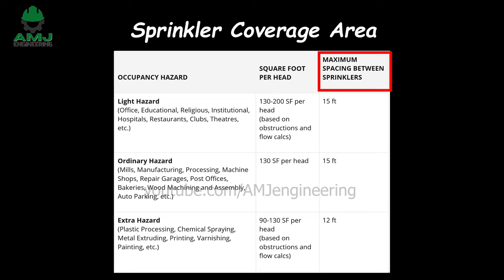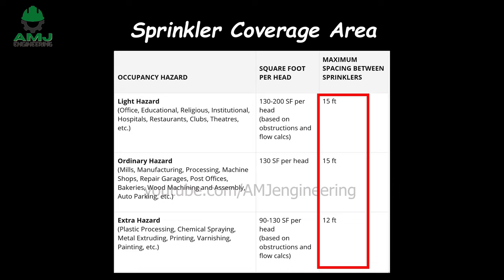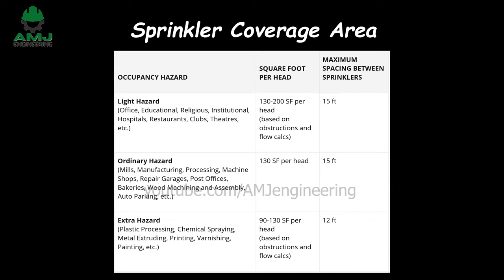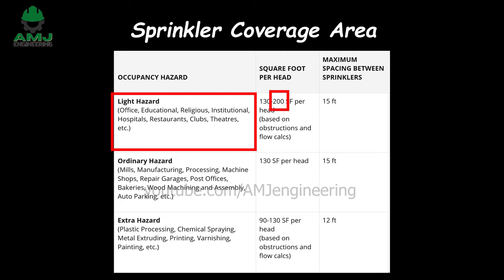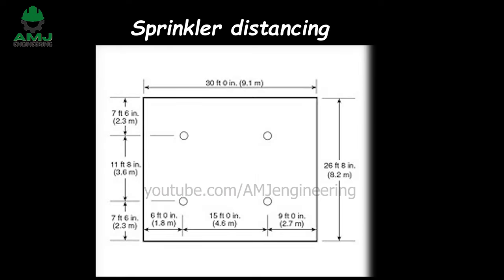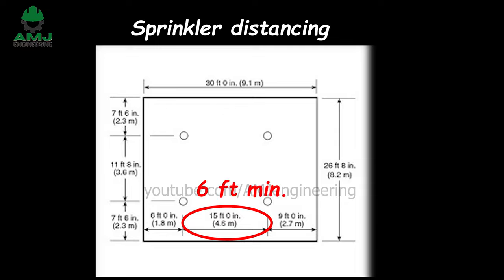Sprinkler head spacing. The table below shows sprinkler spacing requirements based on NFPA 13. For example, in a light hazard office area, the maximum coverage area per sprinkler head is 200 square feet and the maximum design spacing between sprinklers is 15 feet. The maximum distance of a sprinkler head from the wall is half of the maximum distance between sprinkler heads. The minimum distance between sprinklers is typically 6 feet.